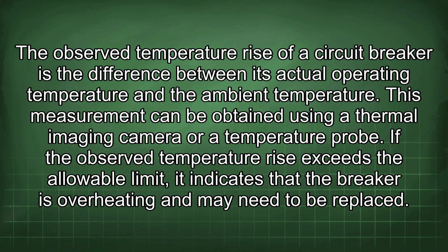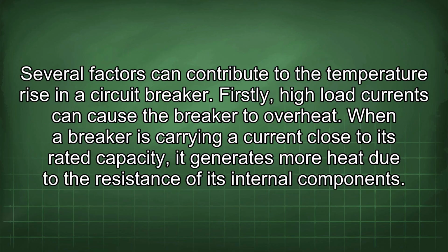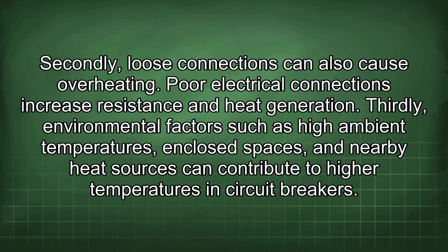If the observed temperature rise exceeds the allowable limit, it indicates that the breaker is overheating and may need to be replaced. Several factors can contribute to the temperature rise in a circuit breaker. Firstly, high load currents can cause the breaker to overheat. When a breaker is carrying a current close to its rated capacity, it generates more heat due to the resistance of its internal components. Secondly, loose connections can also cause overheating. Poor electrical connections increase resistance and heat generation.